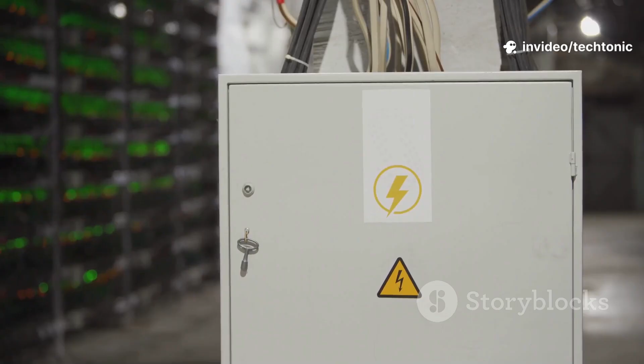Imagine a world without grounding. Some older or industrial systems actually work this way. In ungrounded systems, a fault doesn't cause a big current surge, but it dangerously raises the voltage on other wires, stressing insulation and equipment. The system becomes unstable, just waiting for a second fault to cause disaster.